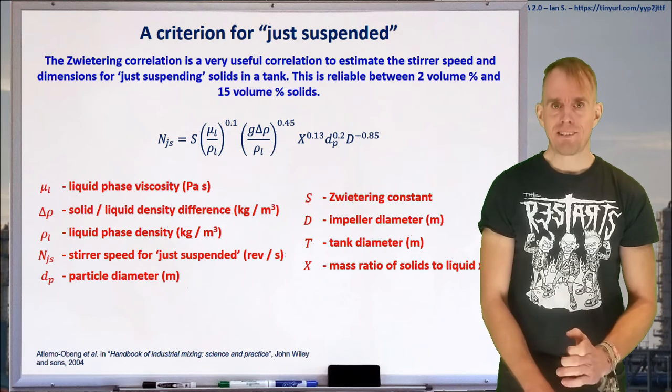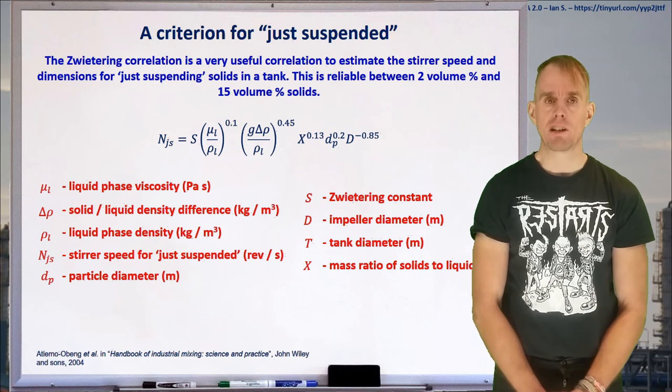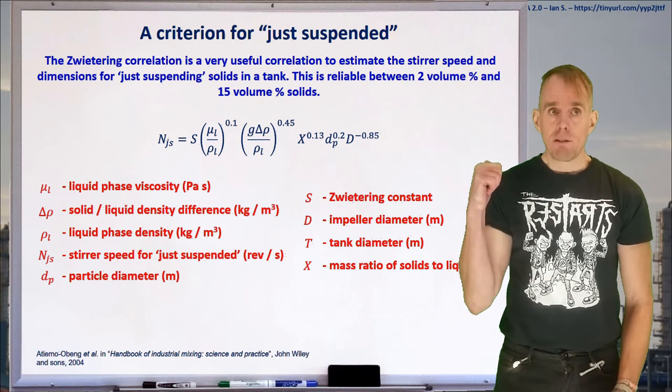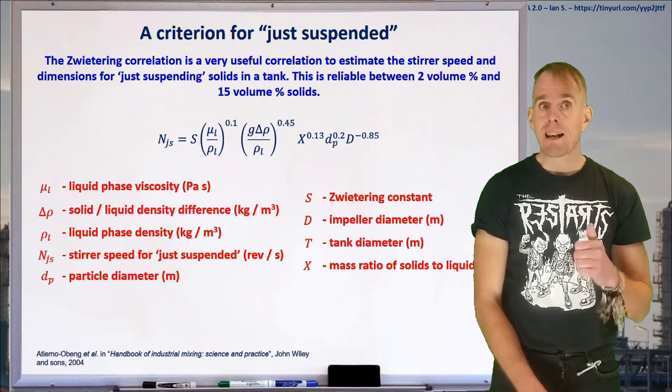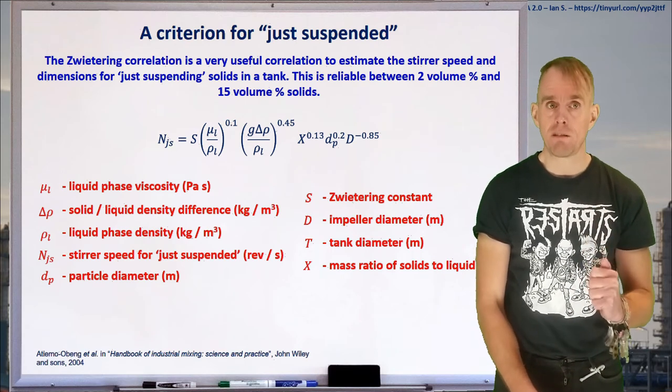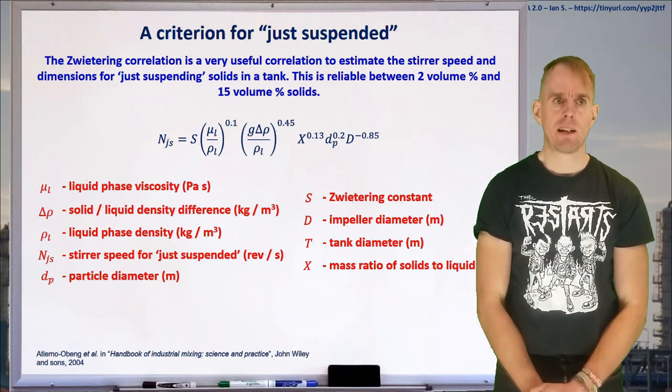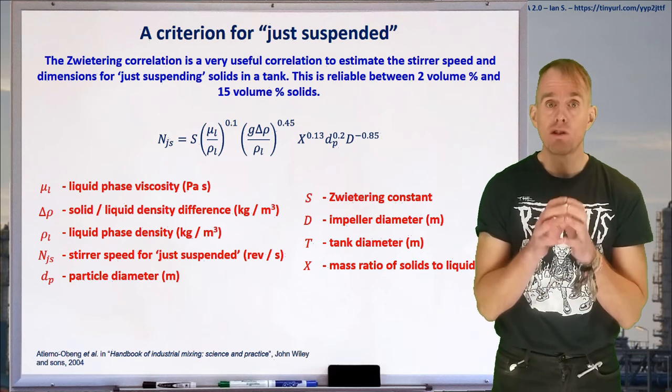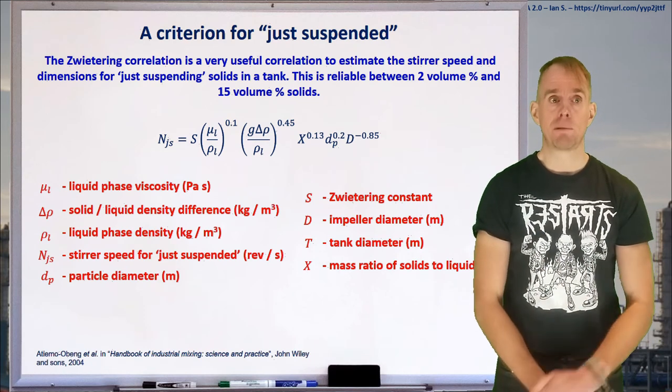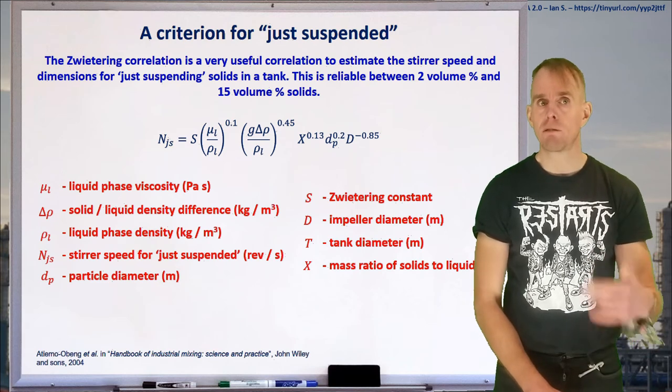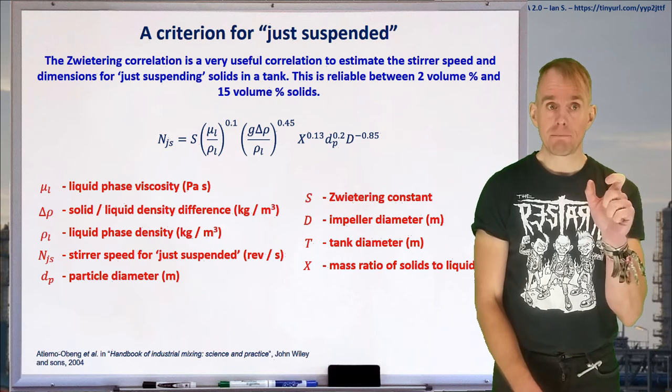Let's think now how we estimate this just suspended criterion. And we've got a correlation called the Zwietering correlation that allows us to do that. Here on the whiteboard, I have put the Zwietering correlation. It's reliable between 2 volume percent and 15 volume percent of solids, and allows you to estimate the just suspended criteria for a given stirrer geometry. Let's look at this in some detail. NJS here is your stirrer speed required for just suspension. And notice this is in revolutions per second.